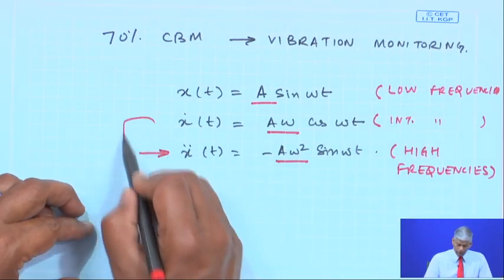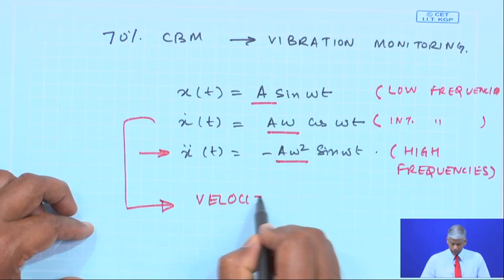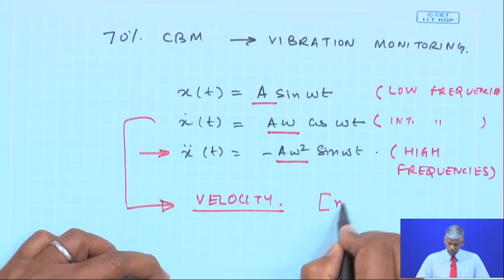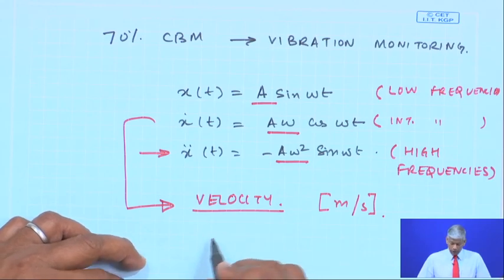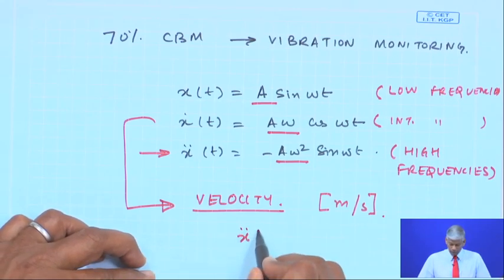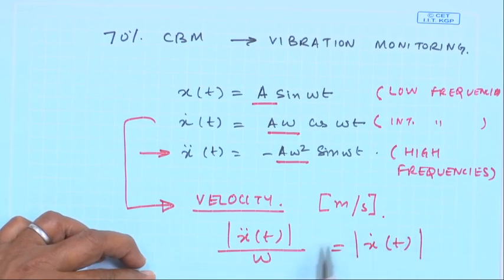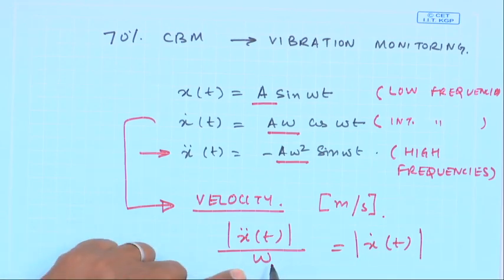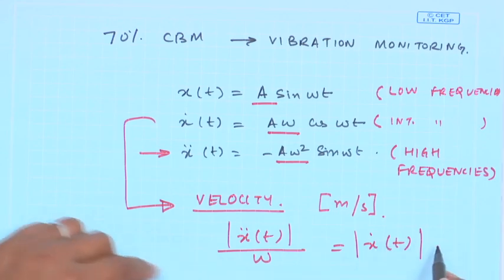At intermediate frequencies we need to measure velocity. Now, there are many standards which use velocity as a parameter, so many measurements have to be reported in velocity. However, if I measure acceleration, dividing it by ω gives the velocity amplitude. So by measuring acceleration and dividing by frequency ω, I can get the velocity amplitude ẋ(t).